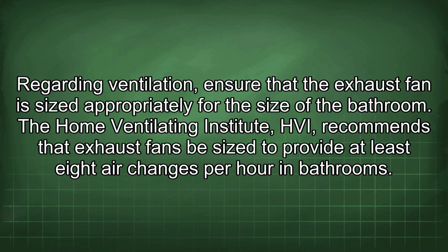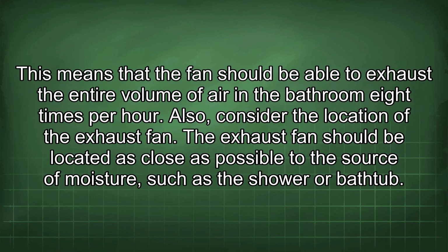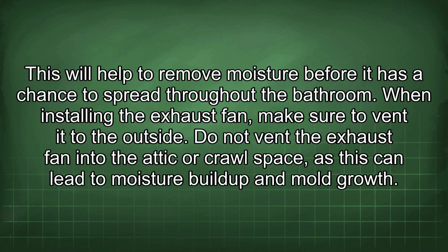Regarding ventilation, ensure that the exhaust fan is sized appropriately for the size of the bathroom. The Home Ventilating Institute, HVI, recommends that exhaust fans be sized to provide at least 8 air changes per hour in bathrooms. This means that the fan should be able to exhaust the entire volume of air in the bathroom 8 times per hour. Also, consider the location of the exhaust fan. The exhaust fan should be located as close as possible to the source of moisture, such as the shower or bathtub. This will help to remove moisture before it has a chance to spread throughout the bathroom.